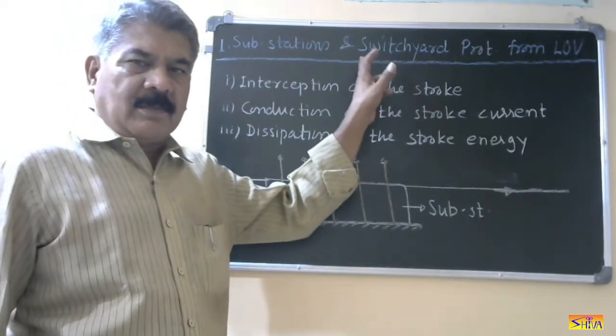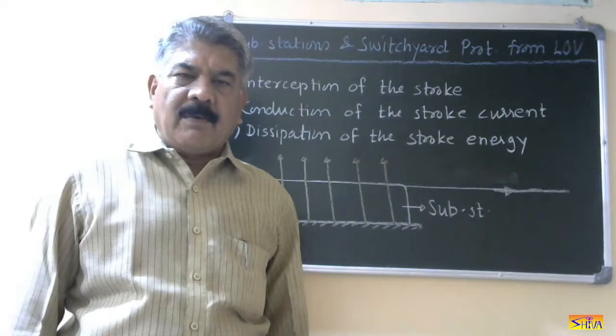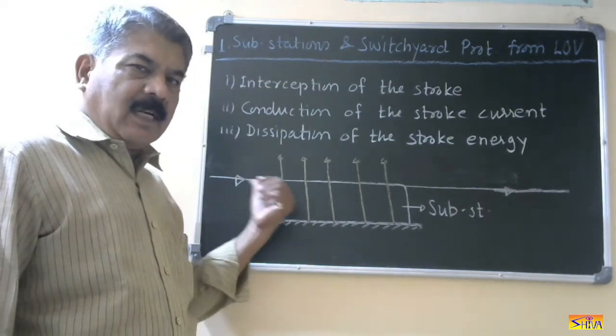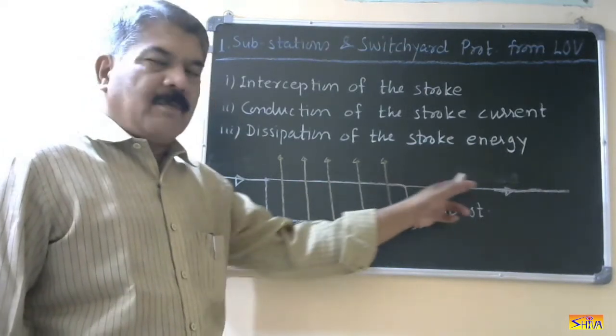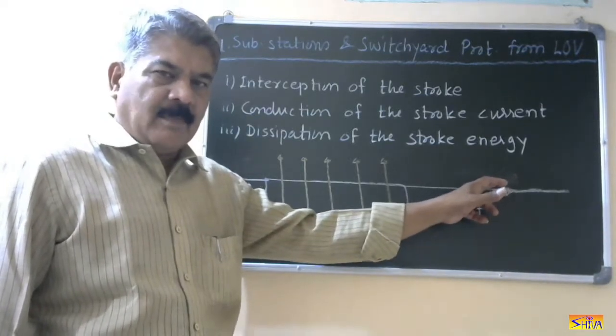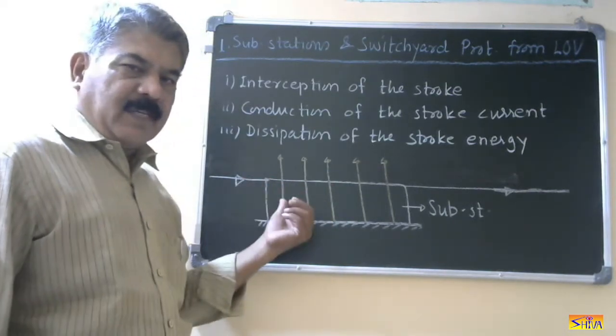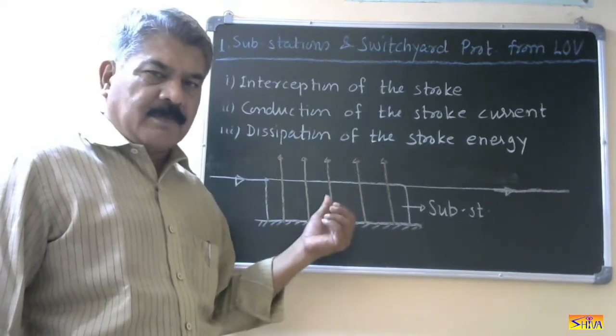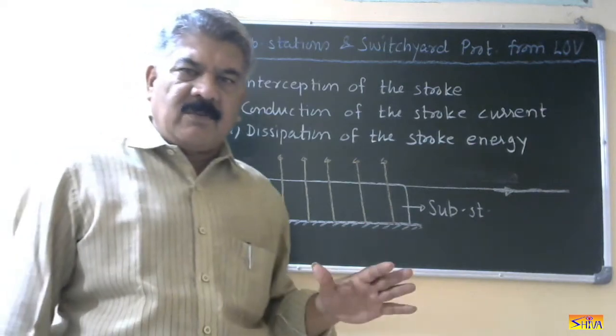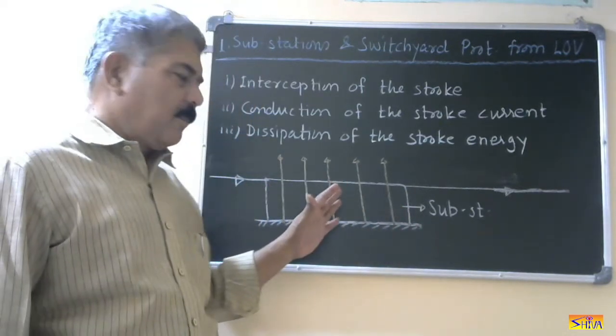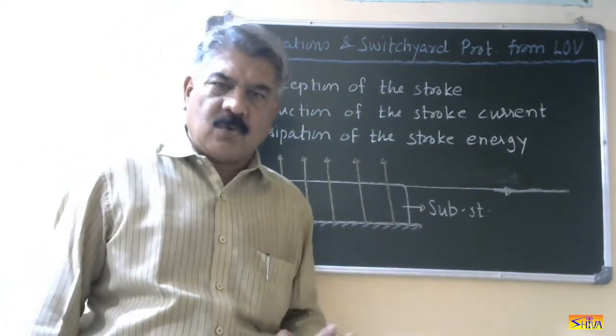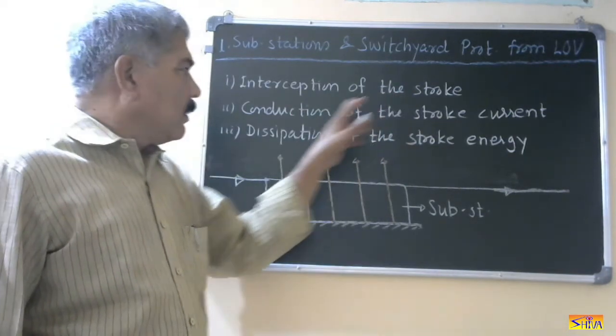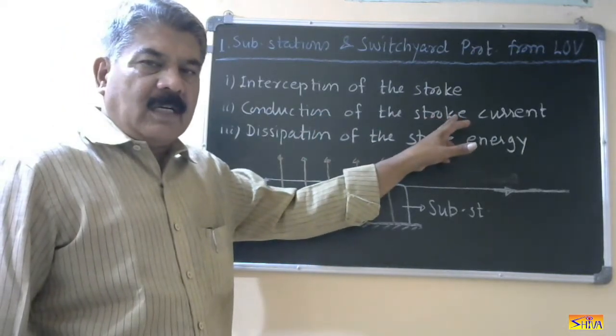The substation is just outside the power station. In a switchyard, the generator is connected, then there is a transformer and other equipment, which is then connected to the transmission system. If it is a substation, it receives power from transmission lines and supplies it to distribution lines via a step-down transformer. Protection of switchyards and substations against direct lightning strokes requires three steps: number one, interception of the strokes; number two, conduction of the stroke current; and number three, dissipation of the stroke energy.